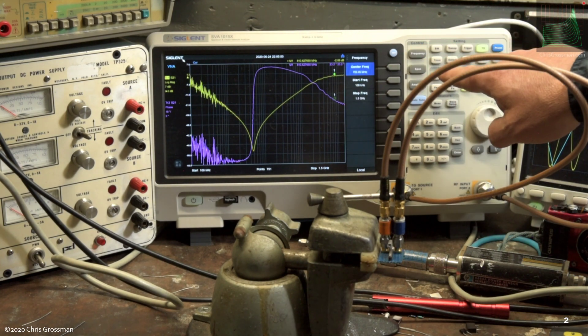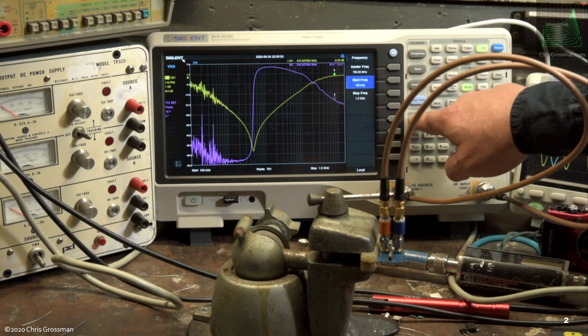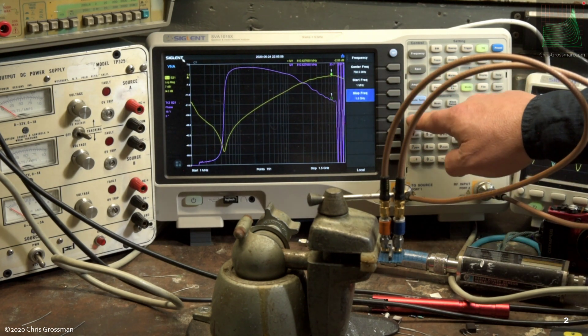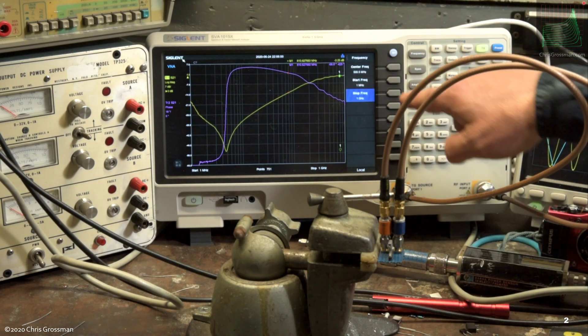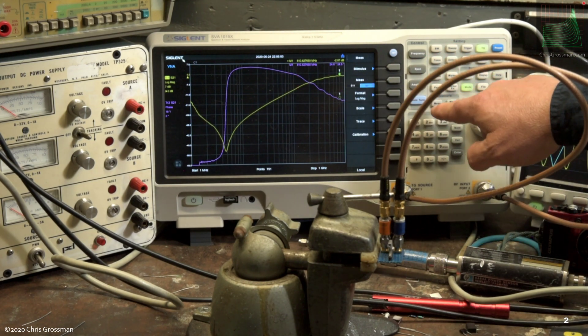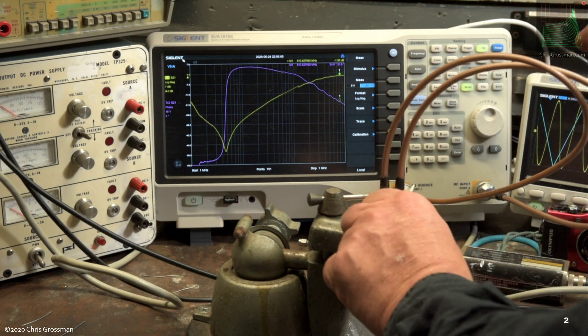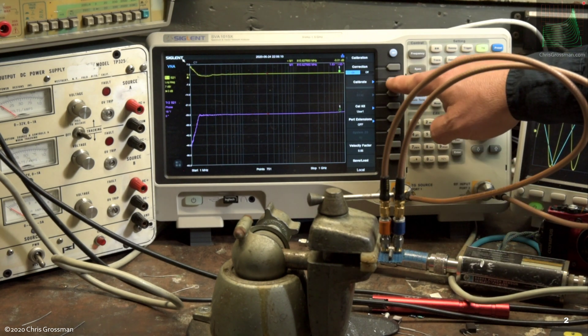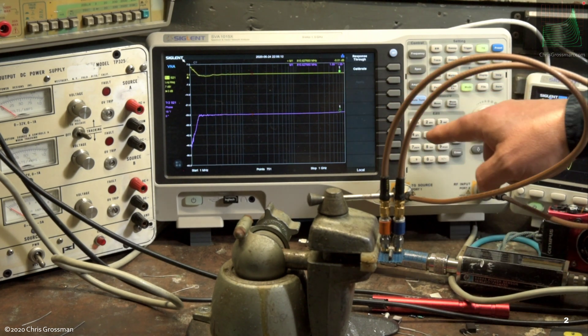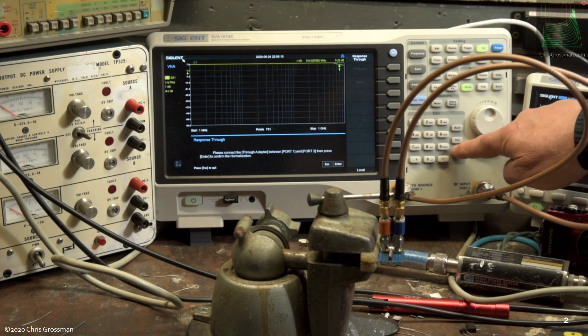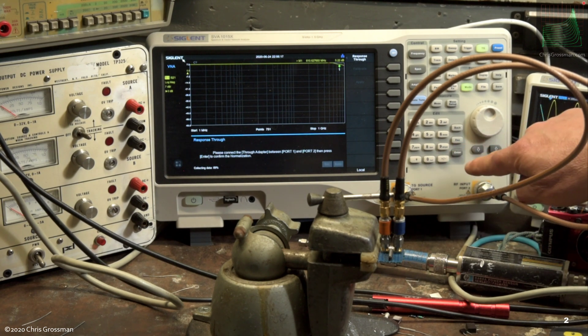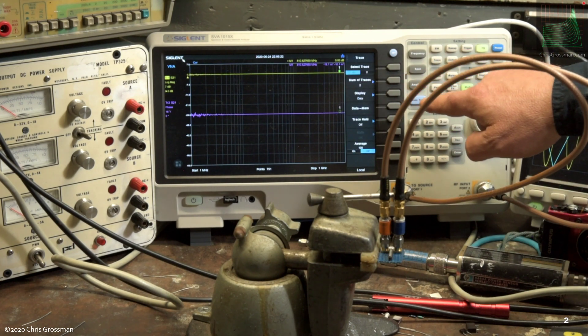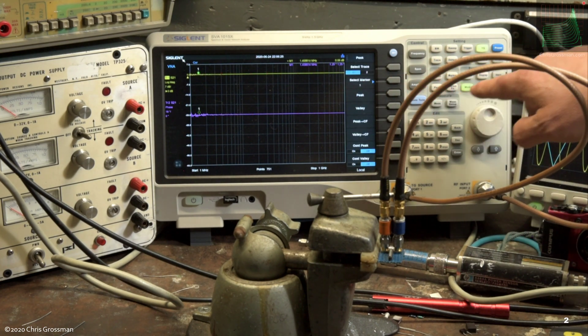To do that, I hit the frequency button, hit the start frequency, select 1 megahertz, hit the stop frequency button, hit 1 gigahertz. Then I have to calibrate the fixture now. So I just do a through cal with nothing in the fixture. So now I've done the through cal. I'll turn the traces back on and go to peak mode.